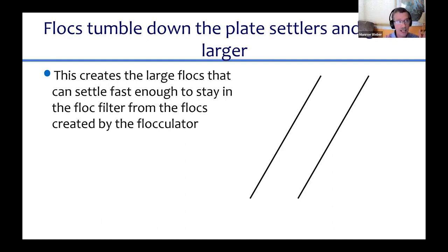And in most modern sedimentation tanks, the water is flowing up. The reason the flocs didn't stay in the bottom of the sedimentation tank initially is because they didn't settle fast enough to stay down. So how do they ever get to the bottom? The only way is if they gang up together and get a higher terminal velocity. Isn't that interesting? That's what's happening inside these plate settlers. It's been happening for decades and nobody talked about it because we didn't really think about what allows these particles to get back to the bottom of the sedimentation tank.